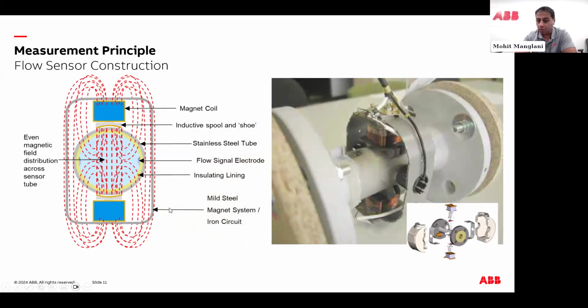So just to give you a feel of what a magnetic meter looks like on the inside, this basically shows you on the left-hand side what the magnetic field looks like and how it's forming through the pipe. And on the right-hand side, you can see a cutaway of an ABB meter. You can see the coils at the 12 and the 6. You can see the coil and the electrodes on the side over here with all the wiring coming up to the top. Some people see these big tubes measuring flow. Well, what's on the inside? This gives you a nice feel for what's on the inside.